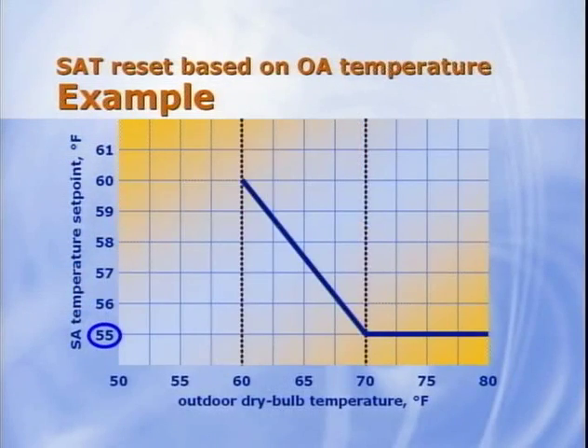Then, when the outdoor dry bulb temperature is between 60 and 70 degrees Fahrenheit, the supply air set point is reset at a 2-to-1 ratio. That is, for every 2 degrees change in the outdoor temperature, the supply air set point is reset upward 1 degree Fahrenheit. In this range, reset enhances the benefit of the economizer and it is likely that some zone level reheat can be avoided.